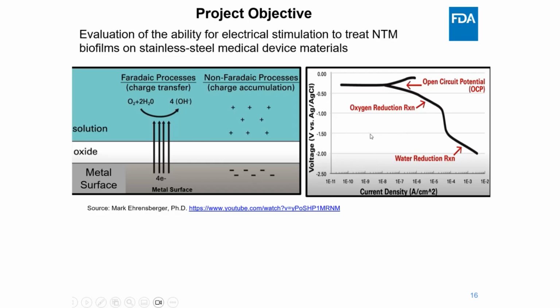The graph on the right shows a polarization curve. The open circuit potential, or OCP, is the natural resting voltage of a metal in solution. So there is no current flow. To trigger biofilm disruptive chemistry, we apply voltage beyond this OCP. So this drives the electrochemical reaction needed to generate reactive oxygen species and disrupt the biofilms. So this gives us a non-antibiotic, surface-targeted strategy for weakening and potentially eradicating NTM biofilms directly at the device interface.